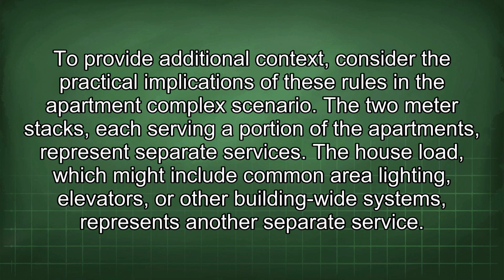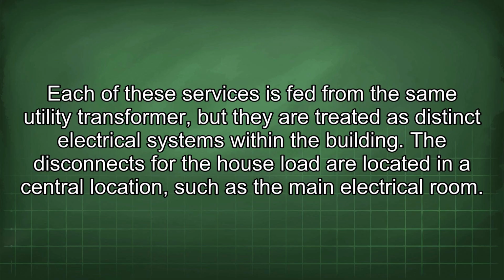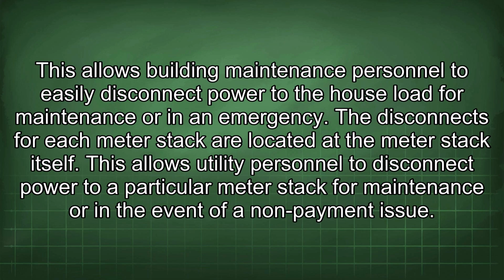To provide additional context, consider the practical implications of these rules in the apartment complex scenario. The two meter stacks, each serving a portion of the apartments, represent separate services. The house load, which might include common area lighting, elevators, or other building-wide systems, represents another separate service. Each of these services is fed from the same utility transformer, but they are treated as distinct electrical systems within the building. The disconnects for the house load are located in a central location, such as the main electrical room. This allows building maintenance personnel to easily disconnect power to the house load for maintenance or in an emergency.